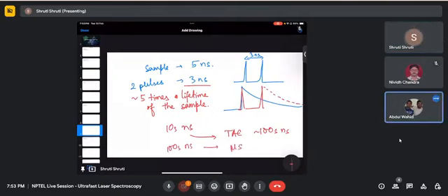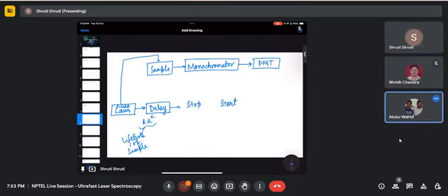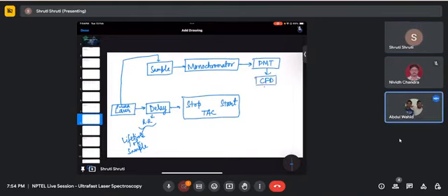Iterative reconvolution is necessary during TCSPC data fitting because of the excitation pulse. Now, the same thing which I explained here. This pulse which is shown here, I'll explain it again. The pulse is not a delta pulse. It will be like this. It's not sharp like a delta pulse. Again, it has some temporal width.